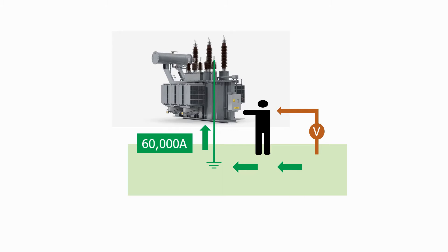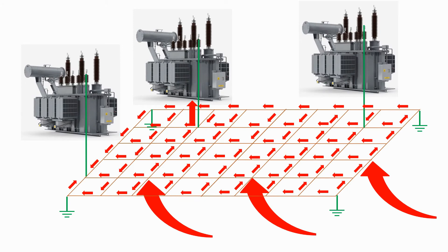To make the substation safe, we install a buried copper mesh across the full area inside the substation. This will provide defined multiple paths for the fault current and allow it to split evenly as it heads on to the neutral of the transformer and equalizes out the ground voltage rise across the substation.